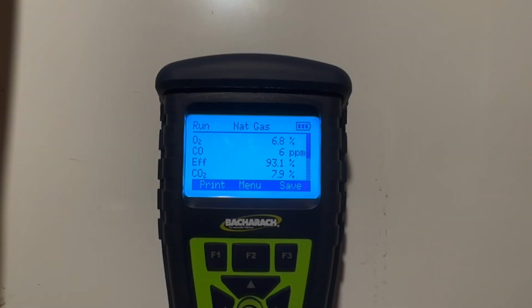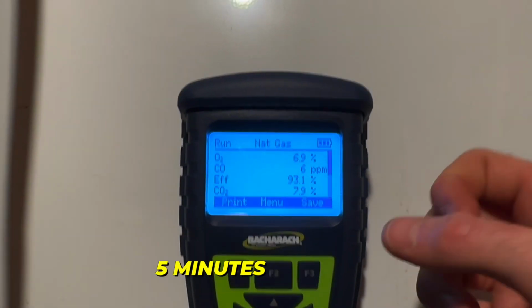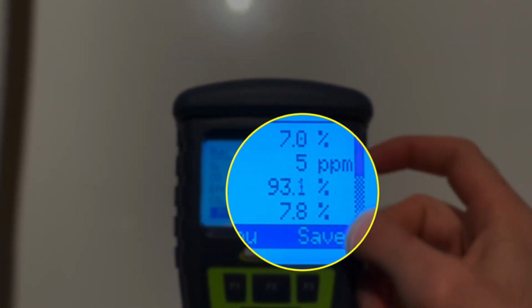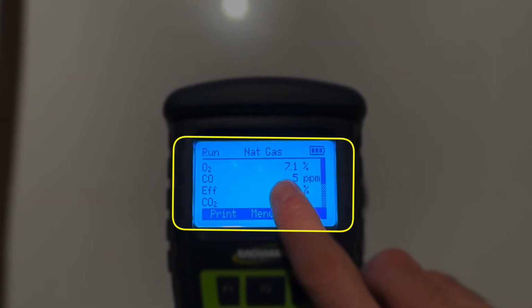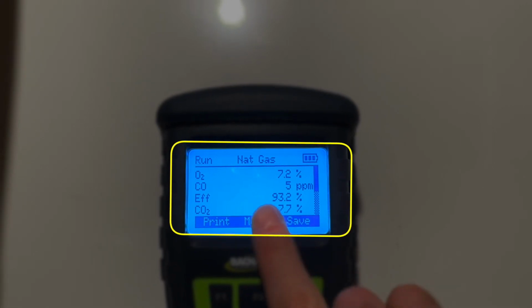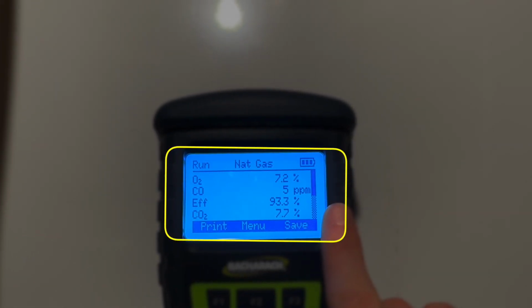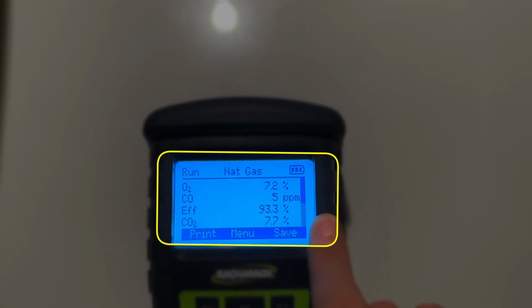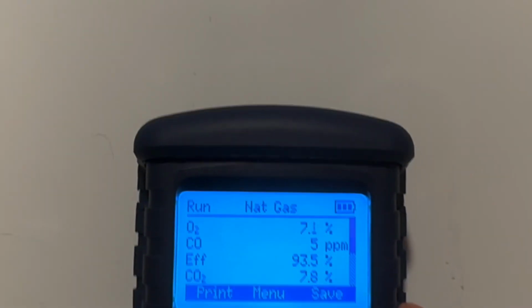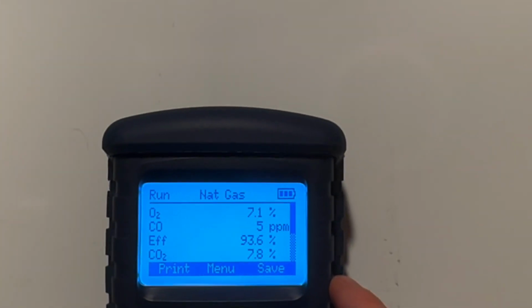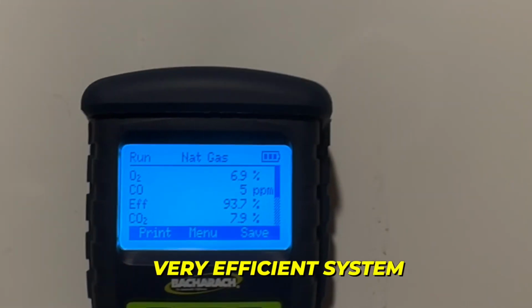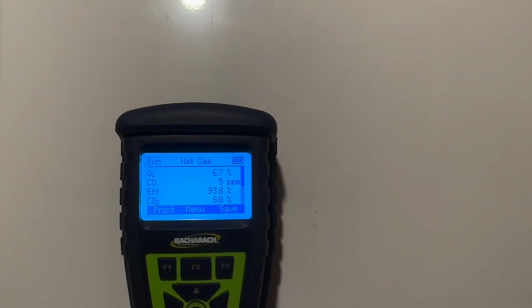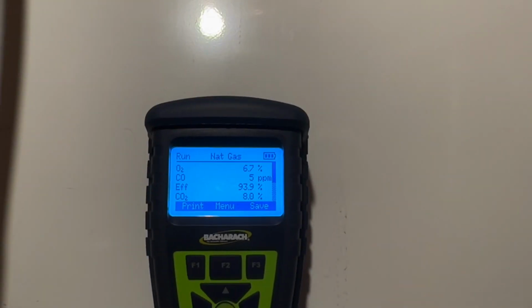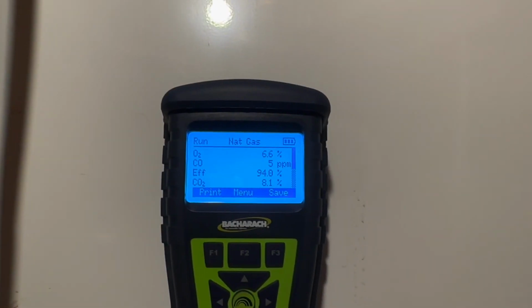It's been running now for about 5 minutes, and as you can see, the efficiency's actually been bouncing up and down. I was waiting for it to climb, but 5 ppm on CO, that's a very clean burn. And then the efficiency's been bouncing anywhere between 93 and 94 while it's running. And again, as you can tell right now, that inducer's running. It's very quiet, very efficient system. Our bedroom's right above this, and we can't hear it up there, so it's really nice. And then you can see it's climbing again.